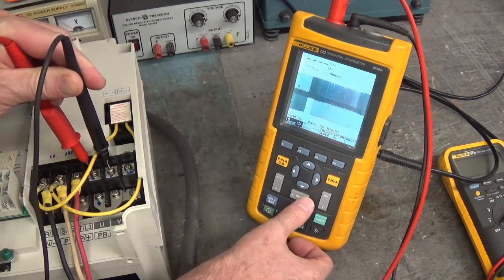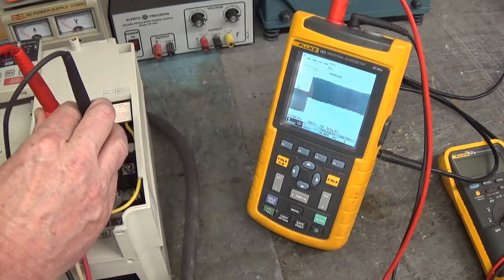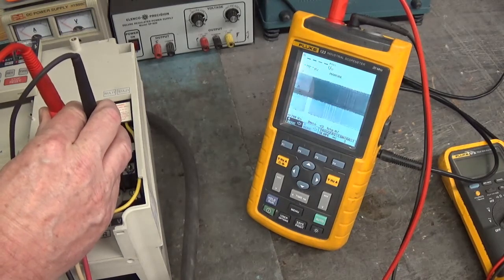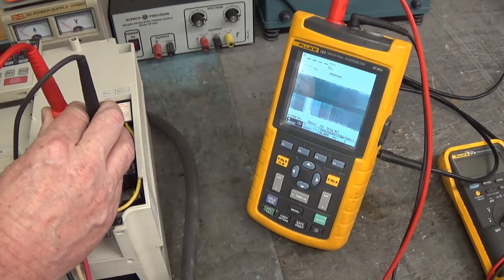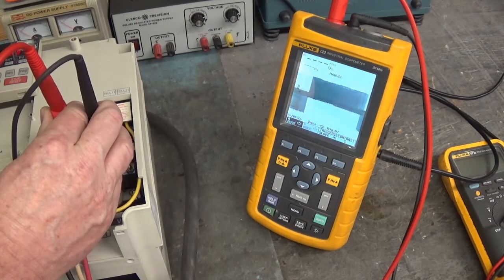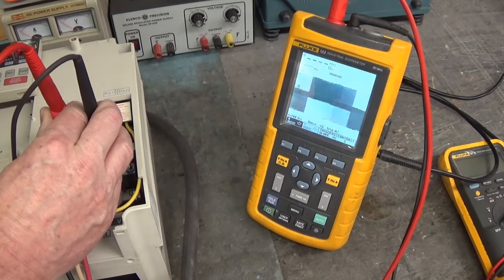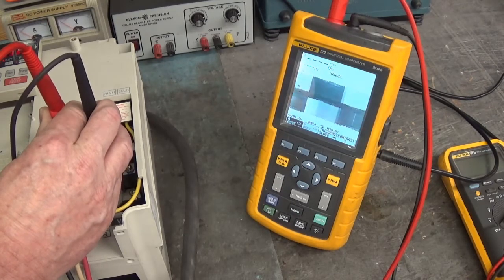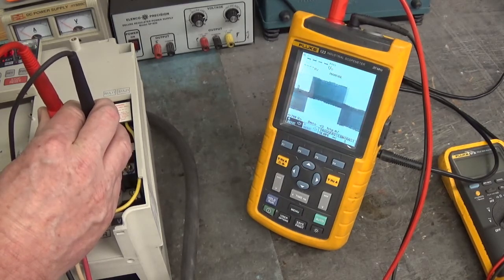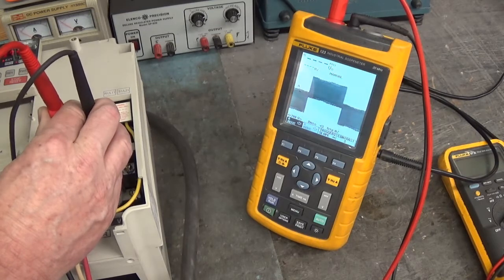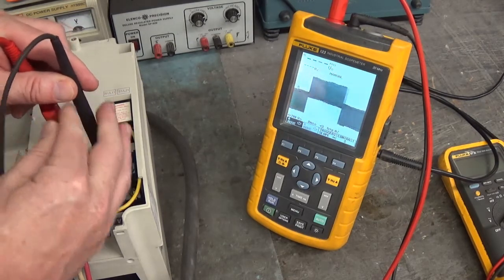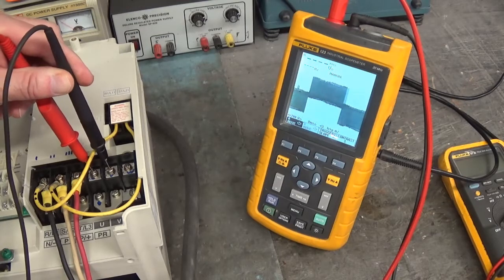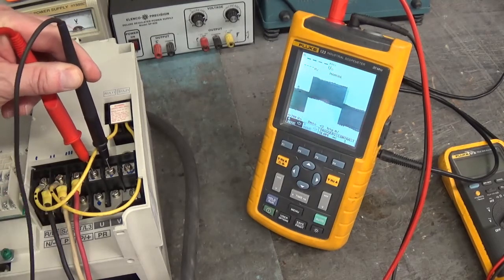Let me speed it up a little bit. Speed it up with the potentiometer until we get good trigger on that display. There we go. That's 53.75 hertz right there. That's looking at U to V.